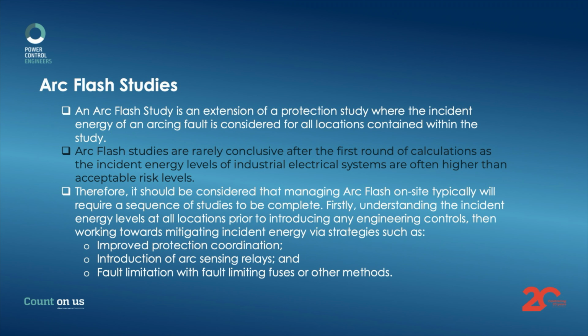Arc flash studies. So we're in 2023, hopefully everyone here has a very good understanding of what arc flash is and the risk involved. So we have to do arc flash studies. An arc flash study is essentially an extension of a protection study. In the case of an arc flash study, incident energy of an arcing fault is considered for all locations within the study. Arc flash studies are rarely conclusive after the first round of calculations, as the incident energy levels of industrial electrical systems are often higher than acceptable risk levels.